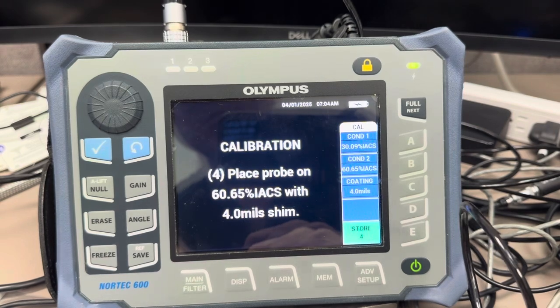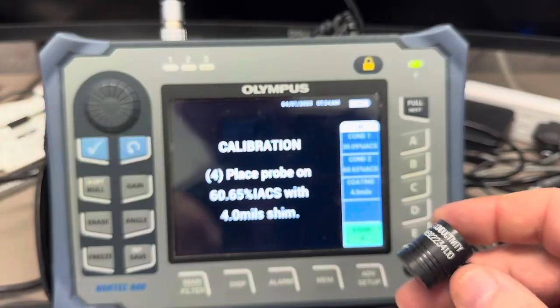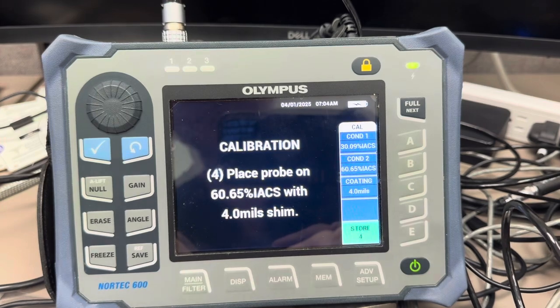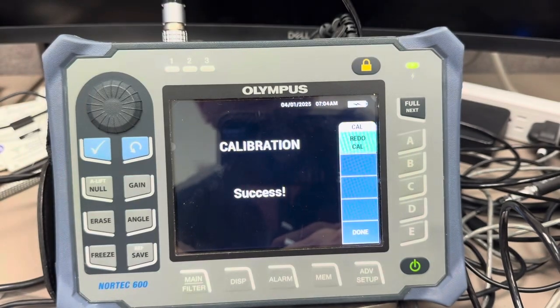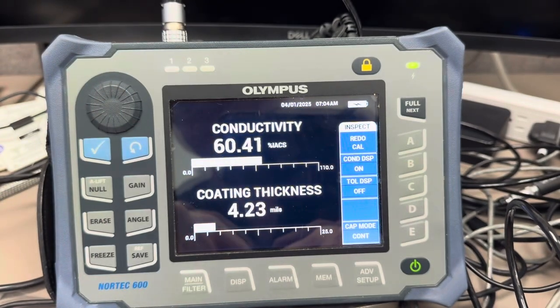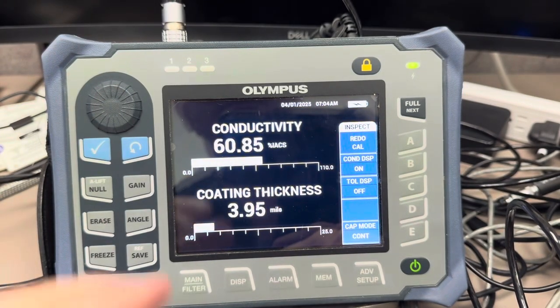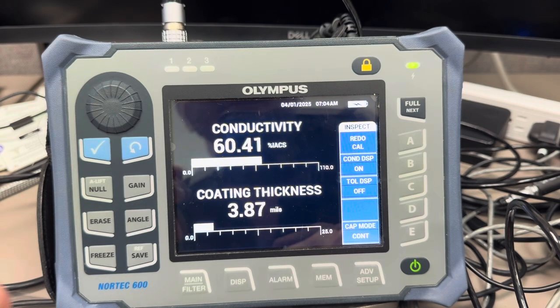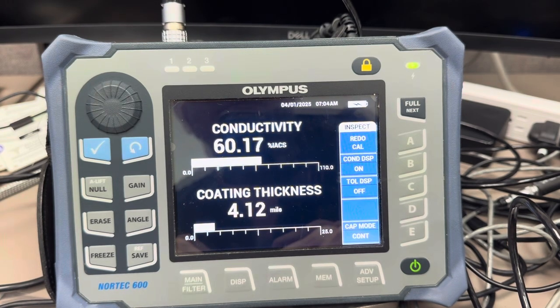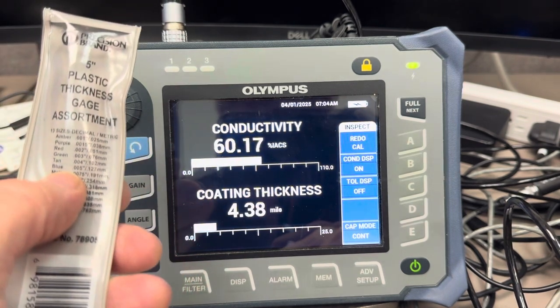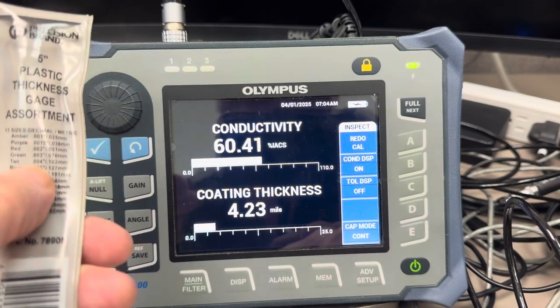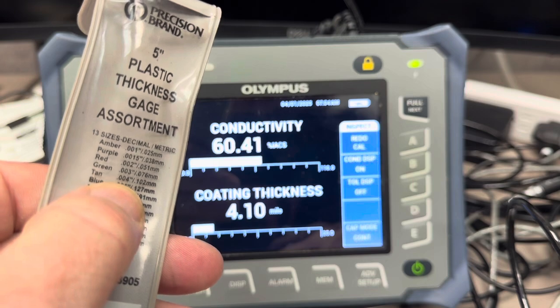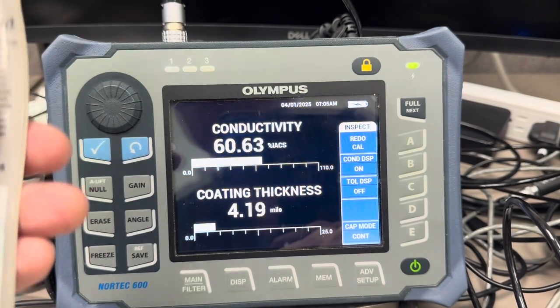And now it's just telling us to move the probe over and place it on top of the shim, on top of the 60.65% IACS, and hit store. Calibration success. That's always good to see. So now I can say done. And without moving the probe, it's saying 60 point, and it's wavering a little bit, but it's close, 60%, right? And it's saying 4 mils. 4 mils is 0.004 inches. And if you look on here for the tan, it's 0.004 inches. So that's 4 mils. So right on, so far it's right on.